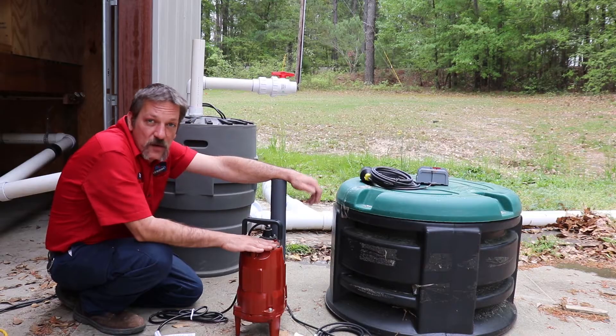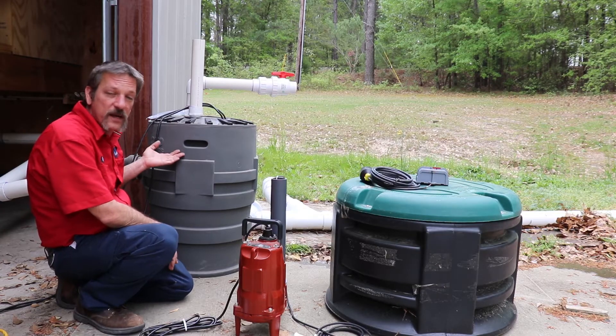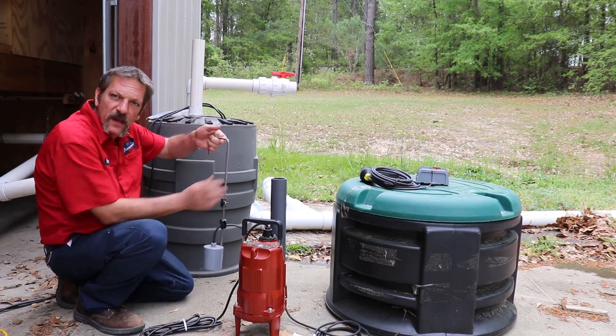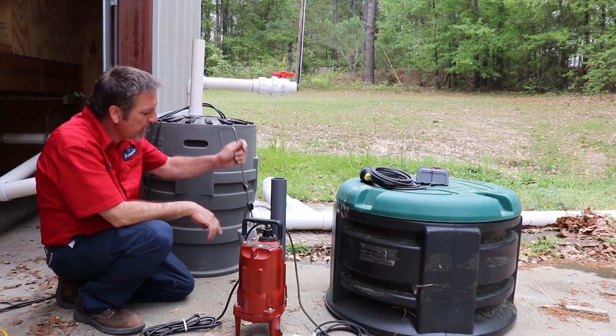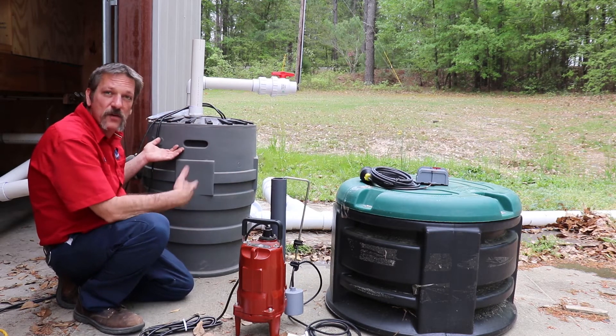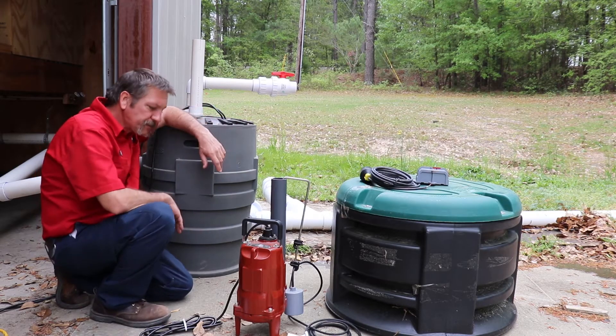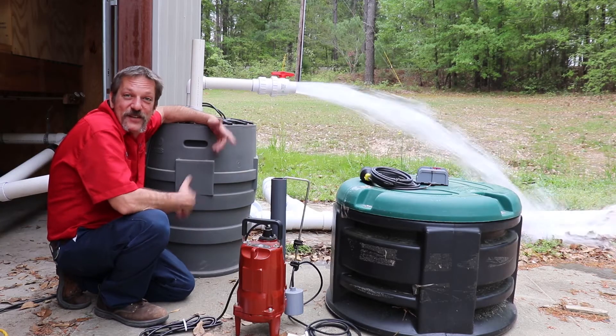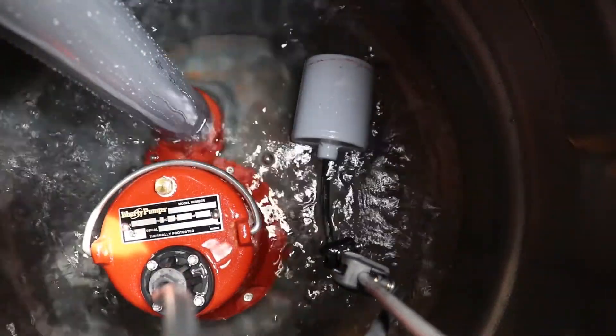You want to be real careful what you flush down your toilets when you've got a pump system. How it works is we've got the 45-gallon crock here. As the sewer water comes in, it starts filling up. It's got a float system, and when that float starts to float and flips over, it makes the connection to turn the pump on. The pump will run until the float flips all the way back over. Even though it's a 45-gallon crock, every time it discharges it's about 40 gallons of water in a matter of seconds.